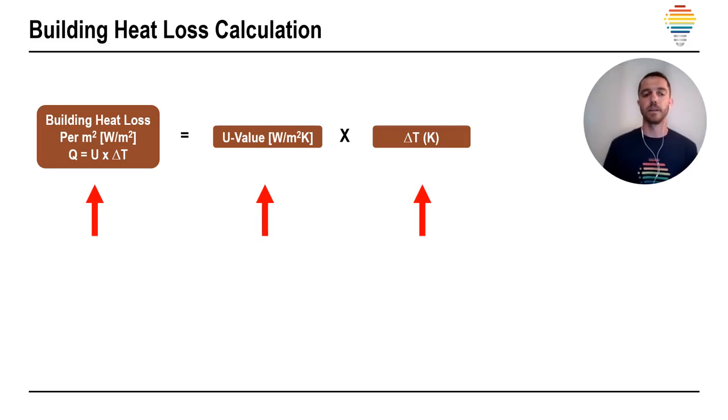For example, if our U value is 5 watts per square meter and our delta T is 30 Kelvin, for example, inside is 20 degrees, outside is minus 10, we have 150 watts per square meter heat loss in that building.